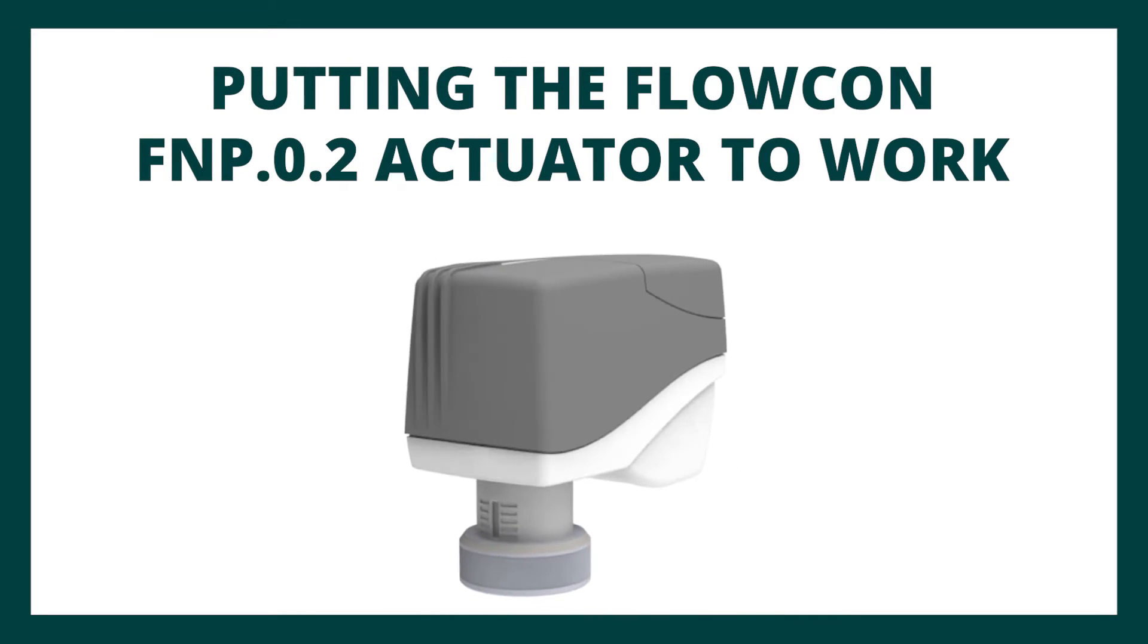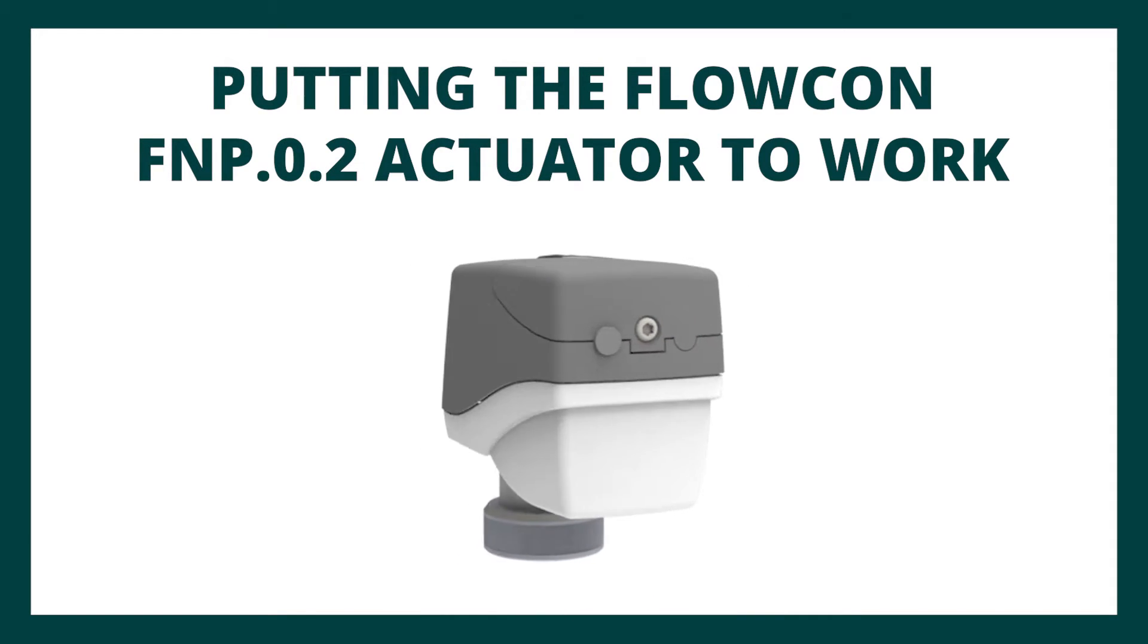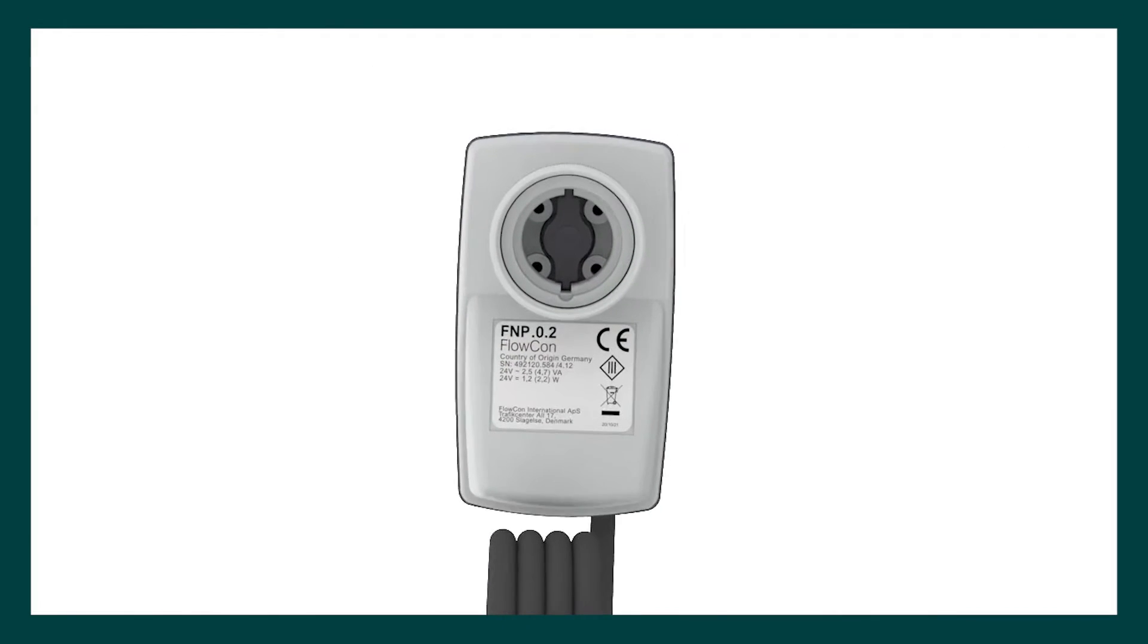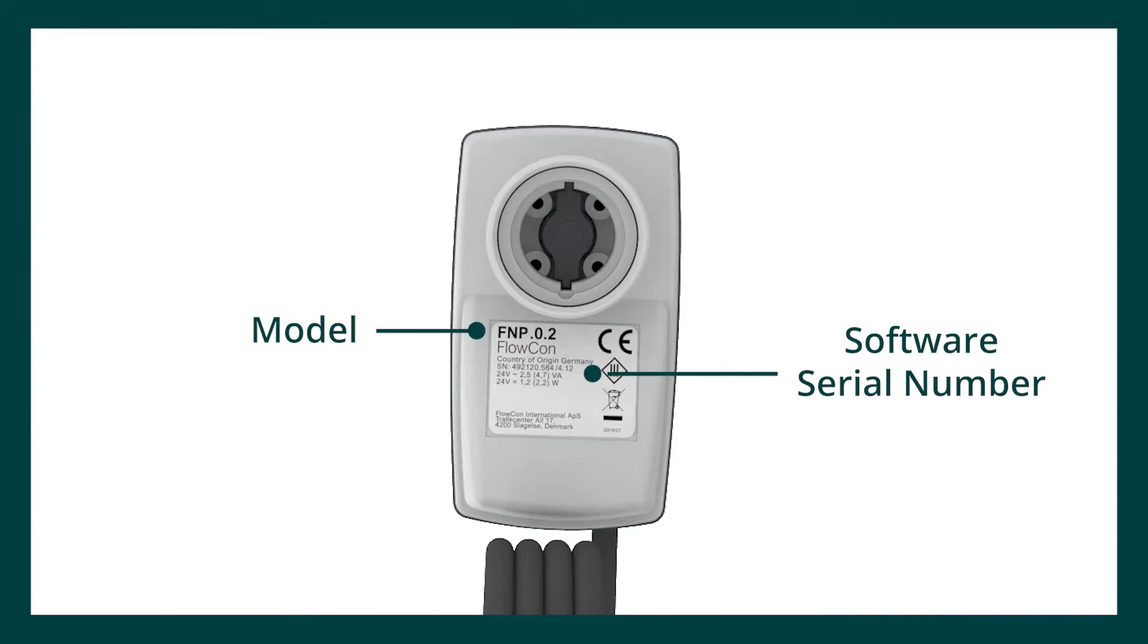The self-calibrating Flowcon FNP0.2 electric actuator is designed for 24V AC-DC with a 10% tolerance and 50 or 60Hz supply with an analogue 0-10V or 2-10V DC signal.